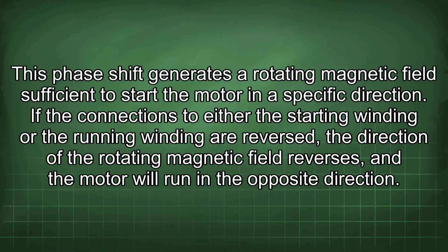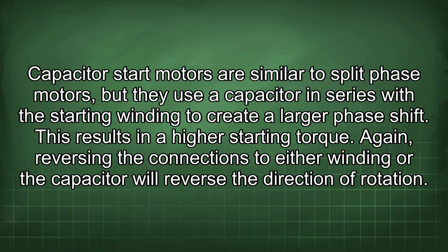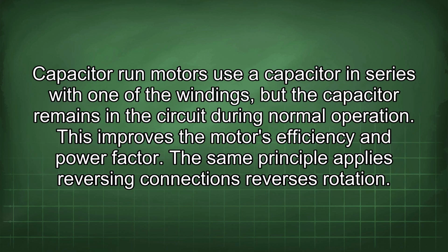If the connections to either the starting winding or the running winding are reversed, the direction of the rotating magnetic field reverses, and the motor will run in the opposite direction. Capacitor start motors are similar to split-phase motors, but they use a capacitor in series with the starting winding to create a larger phase shift. This results in a higher starting torque. Again, reversing the connections to either winding or the capacitor will reverse the direction of rotation. Capacitor-run motors use a capacitor in series with one of the windings, but the capacitor remains in the circuit during normal operation. This improves the motor's efficiency and power factor. The same principle applies: reversing connections reverses rotation.